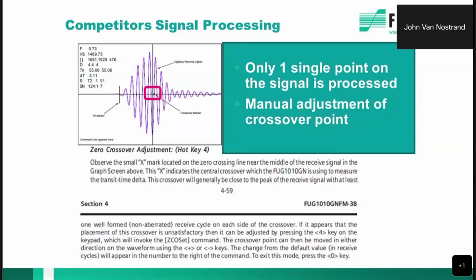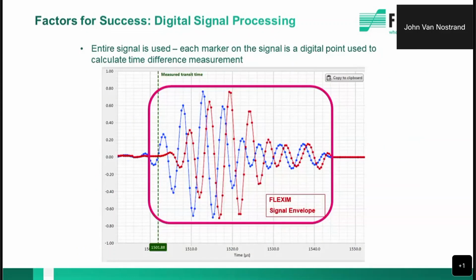But what happens is when the temperature changes of those transducers or the process changes, that actually can find its way outside of that box, because what it normally does is it seeks the highest peak-to-peak value on the sinusoidal waveform, and it places itself in that spot. When that sinusoidal waveform changes, so does the digital mark, and it can actually find its way out of their detection window. So what we do at FLEXIM is we encompass the entire sinusoidal waveform in our signal envelope, and we digitize it multiple times. So instead of putting one digital mark, we put 8 digital marks on every sinusoidal waveform.